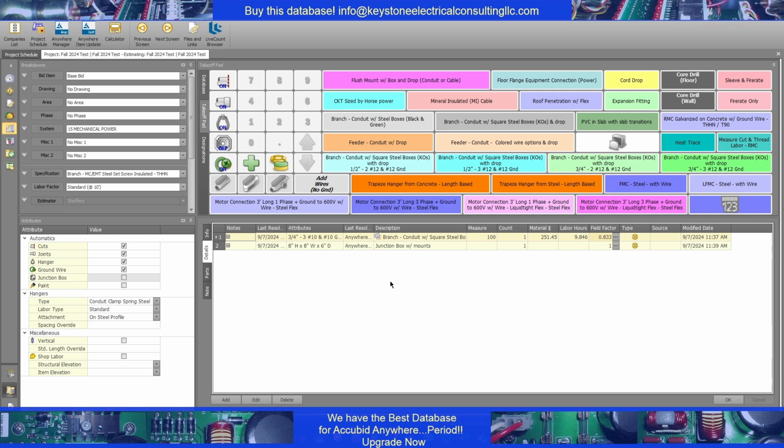Where we really get into the big difference of my database versus anything else, a lot of you would be saying, well, if you're going to change from EMT to PVC, you must have to change the specification because it's a different material type. Under normal conditions, yes, but I acknowledge the real world here. The reality is I'm stuck in this environment where I say I want this to be the end all be all bucket for everything. So I cannot change the spec midstream like this.